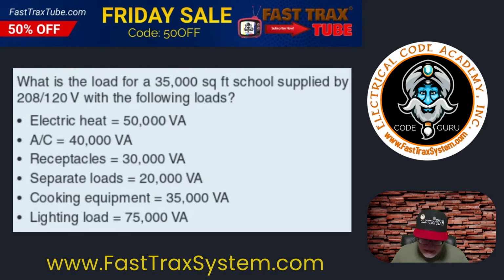We're going to add the 50,000. I'm going to write that down, 50,000. We're going to take the 30,000 for the receptacles. It's already been added up for us. We're going to take the separate loads, whatever they may be, at 20,000. We'll say that's the other loads that are given to us in 220.86. The cooking equipment, 35,000. And then, of course, the lighting load, it's 75,000.